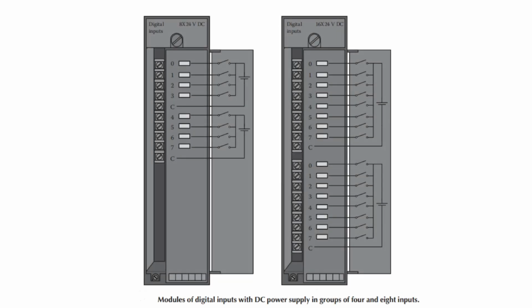Then in the next step, the resulting low level DC voltage is used to power an LED, the light emitting diode, which is integrated with the phototransistor, which creates a logic signal for the microprocessor for its activation. Next is the optical isolation, which ensures decoupling between the input electronics and the microprocessor, and protects it from electric faults and noise and ensures its safety. Next, you can see in the diagram also about all the modules. The modules with large input counts mainly require proper power supply considerations. Inputs can have separate power supplies, which allows us to customize for various input devices with different power sources to connect to the same module. Alternatively, inputs may share a common power source, which necessitates grouping by common voltage nodes.